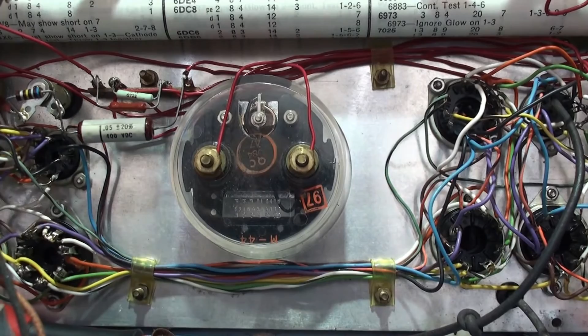I mean, basically anything else on here can probably put up with it, but the meter is the one piece of instrument that won't put up with a large amount of current. And it will also be a good idea to possibly put a capacitor across there, as long as it doesn't affect the response of the meter, because what that does is slug the response of the meter down considerably. And what that allows you to do is, if you've got a sudden short and the meter wangs over to one side, it can actually mechanically damage the meter.